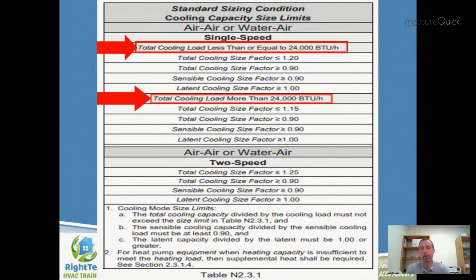For a single stage unit, instead of the old 15%, if you've got a load of less than 24,000, you can now have a factor of 1.2 or a 20% oversizing factor there. And that's not that we're trying to encourage people to unnecessarily oversize equipment, but when you really break down and look at the math between, say, a nominal 18,000 BTU per hour system, 1.5 tons, versus a 2 ton at 24,000 BTUs per hour, that's almost a 30% jump.